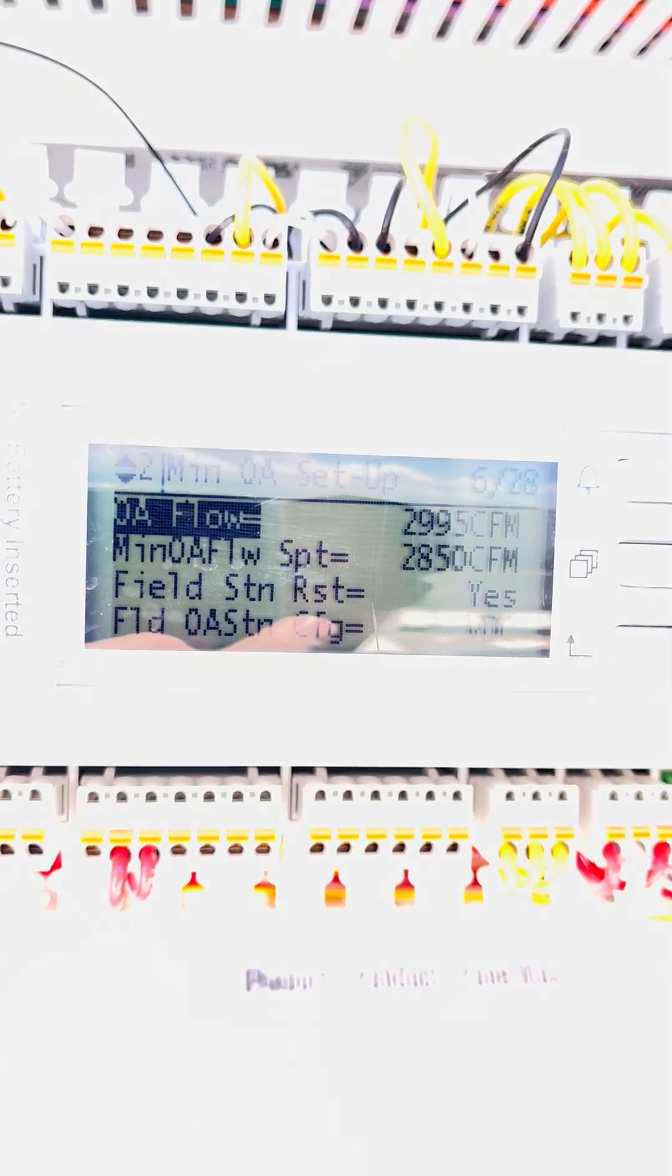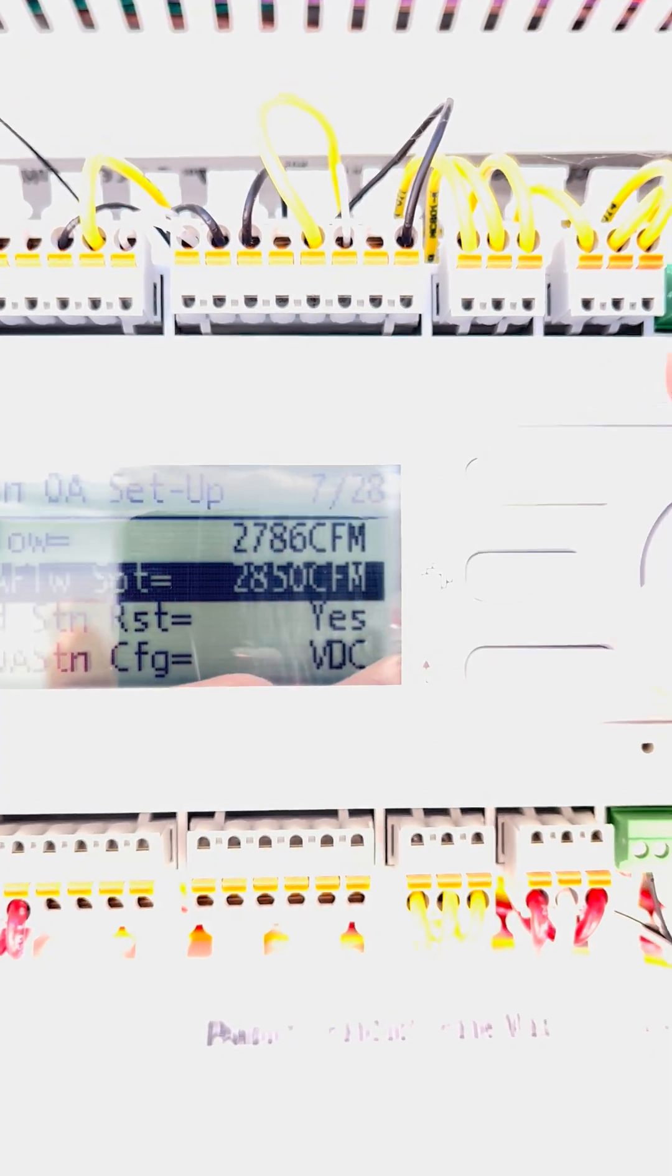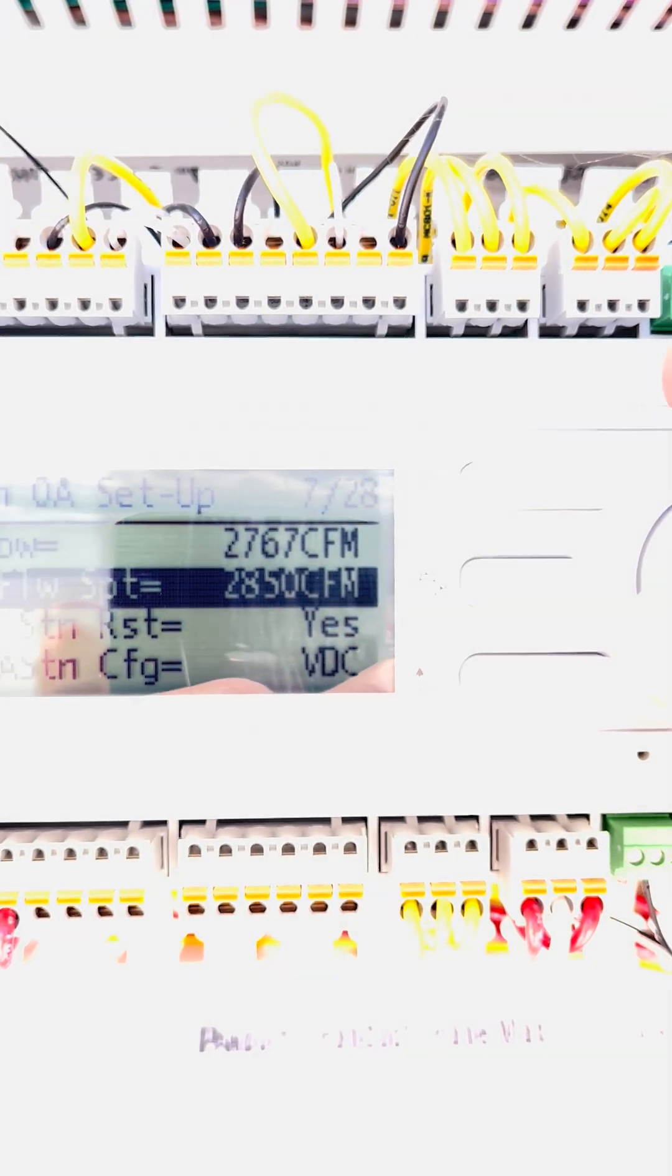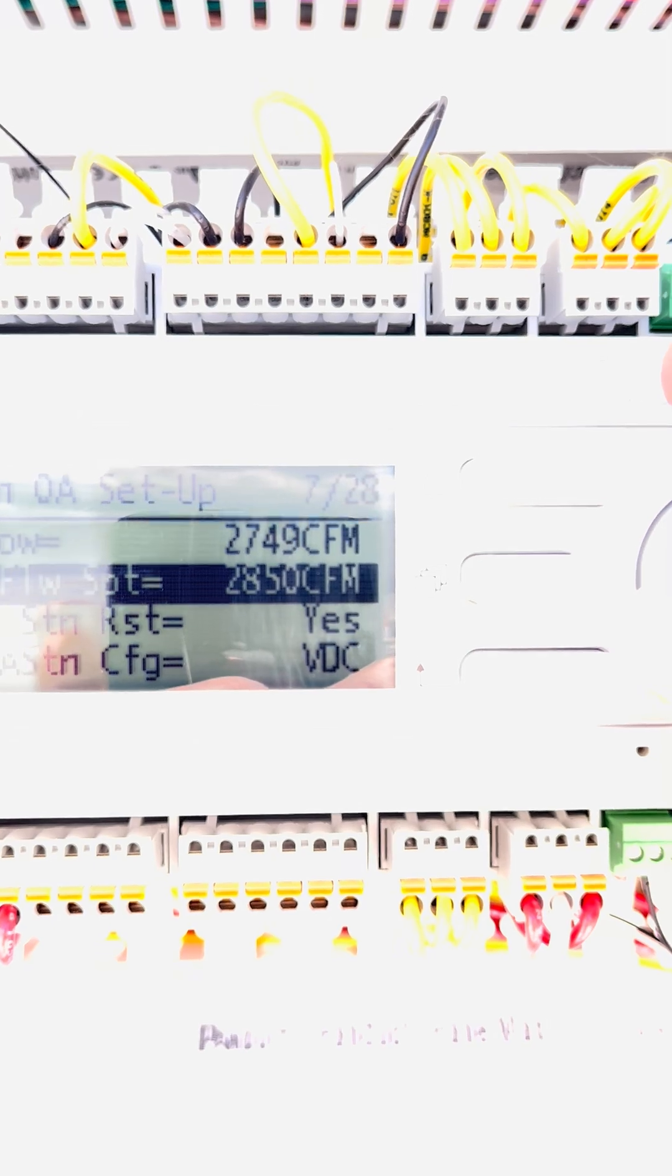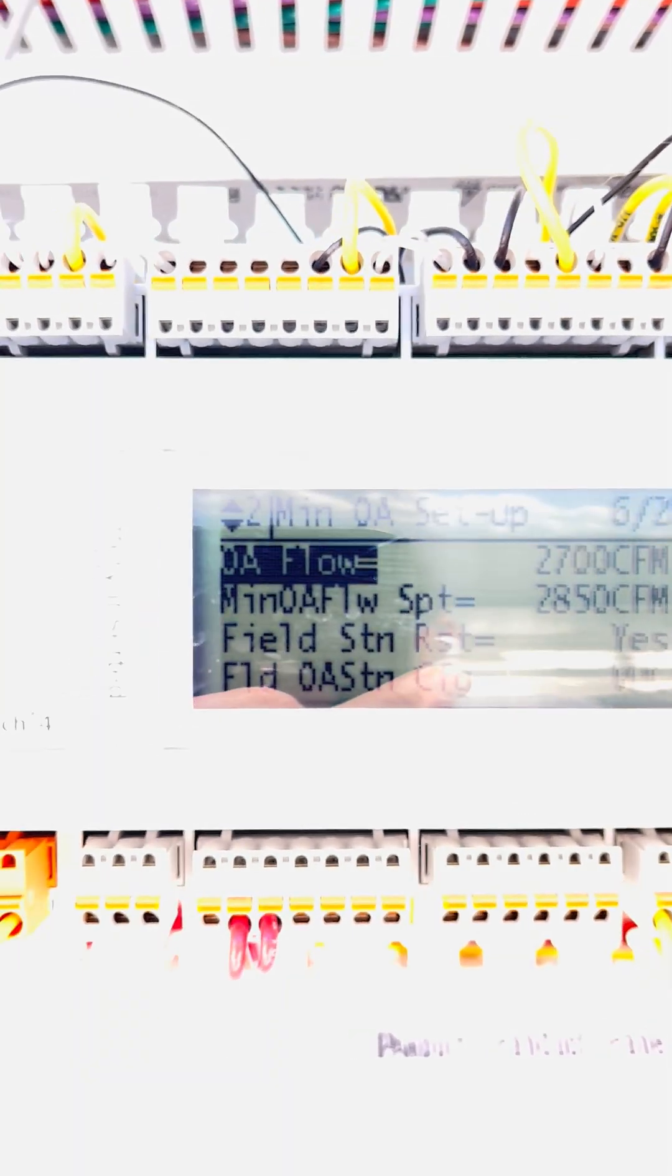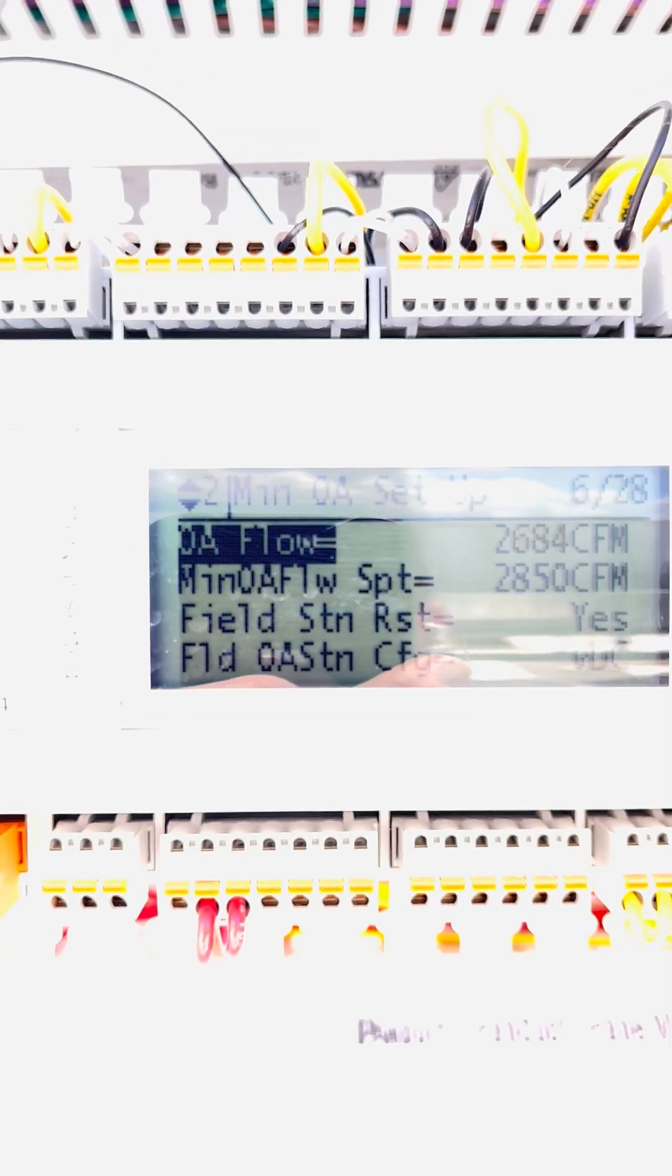And then outside of that, this is also where you set your min CFM set points. 2850 is what they requested. Notice how we're pretty close on the money there, 2727. This is your live value of outdoor air flow.